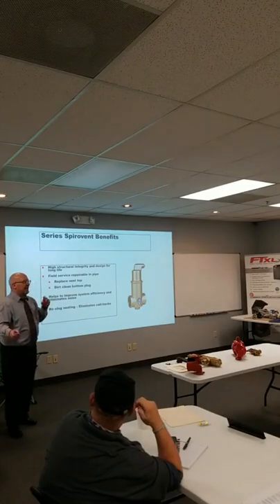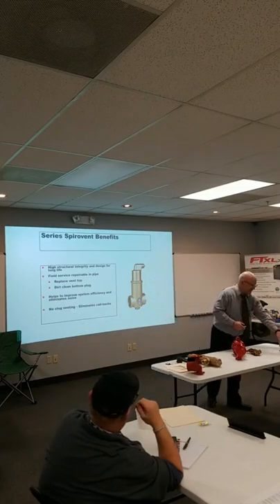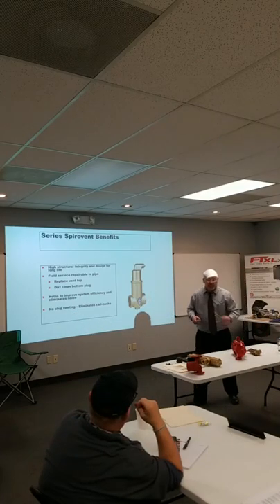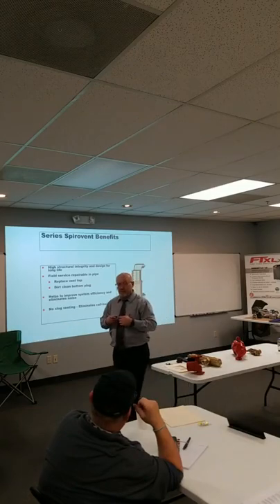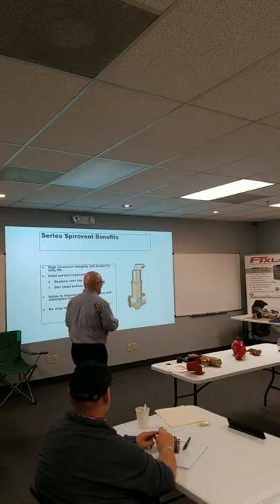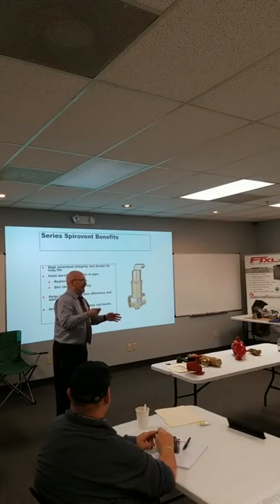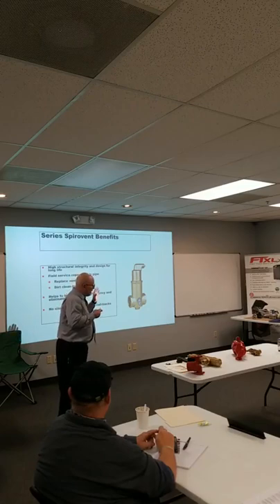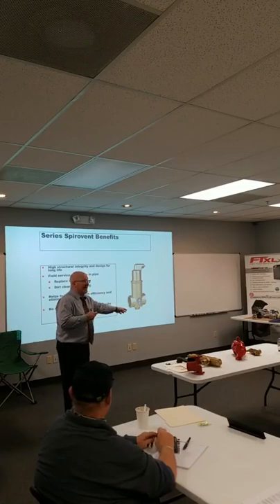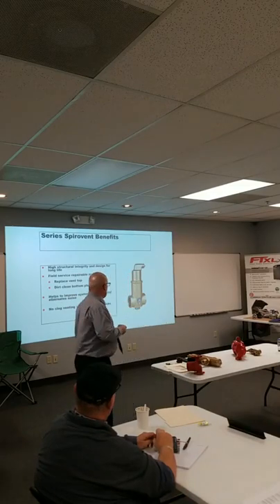But good air separators to me are an insurance policy, guys. Get rid of the air. Air is what's causing this ferrous oxide to grow, and it's basically the deterioration of your system. Air is an insulator, so it's not helping our heat transfer. Air and water running through a pipe, you can hear. If the air's out of the water, you can't hear water running through a pipe, unless it's totally undersized. If you have a normal system and you hear water running through radiators, they've got air in it. Get rid of the air. It doesn't do us any good.